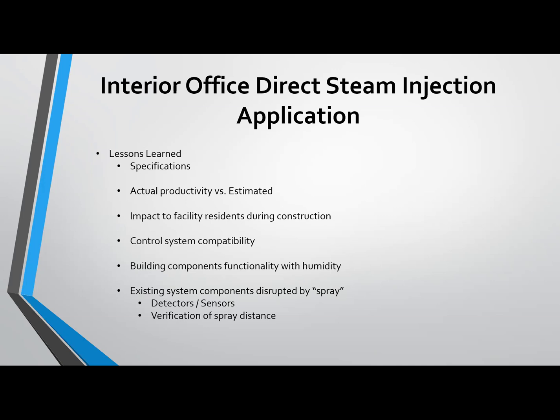And then the last big lesson we learned was that when you put in direct steam injection, it is a very violent spray of stuff. It's not a lot, but it's carried by air and by fan, and these moisture droplets go down the duct as they disperse into the space. Any type of detector -- be it a smoke detector, temperature sensor, airflow sensor, anything in the path of that direct spray right as it comes into the duct -- needs to be looked at closely, to consider whether we really need it there.